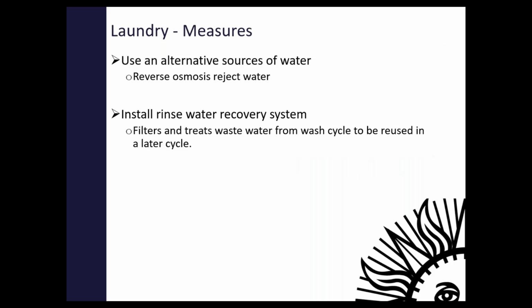You don't want to continuously pump new water into your laundry system if it's almost continuous use. So here, if you have a hospital where you need reverse osmosis water for procedures, for humidifiers, or things like that, you can use the reject for your laundry. You have to treat it a little bit, soften it, but overall you can use that. It becomes an effective source if you have large amounts of laundry being done. And then, of course, you can install a final rinse water recovery system.